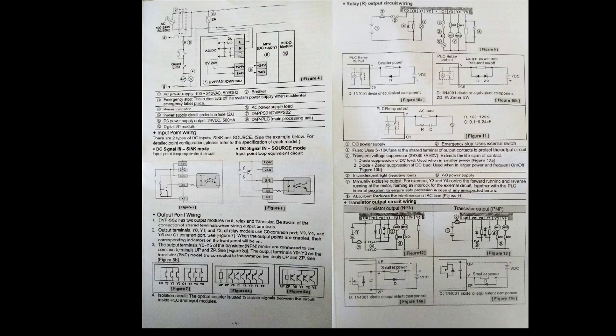The PLC has two modes: sink mode and source mode. I will use source mode. If you want to use inputs with 24 volt DC, you need to connect SS to ground. Connect SS to ground as shown in the relay output circuit wiring. We should give C0 and C1 a positive voltage.